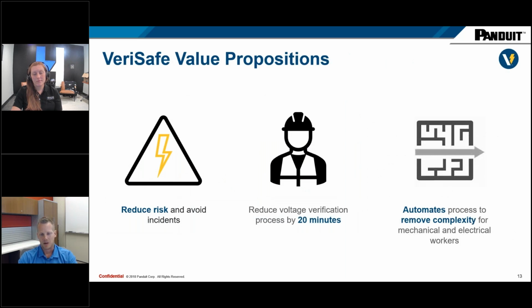Kind of the main value props of VeriSafe, right? First and foremost, it was developed to reduce risk and avoid those incidents, avoid that hazard or that exposure to the hazard. That was the first and foremost reason it was developed. The benefit and outcome of that is it just does it quicker. It saves about 20 minutes, 19 minutes and 50 seconds if you're doing that mental math.